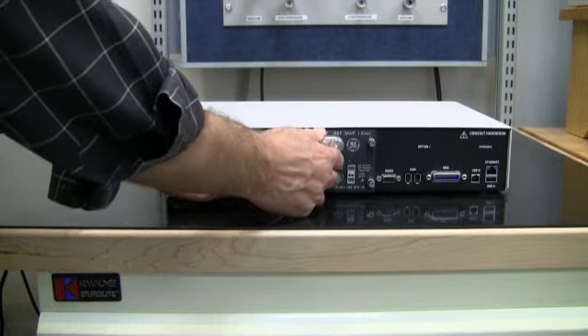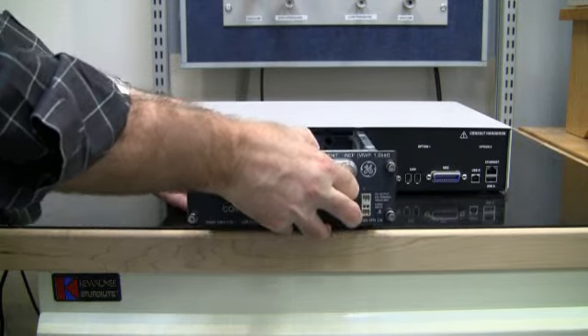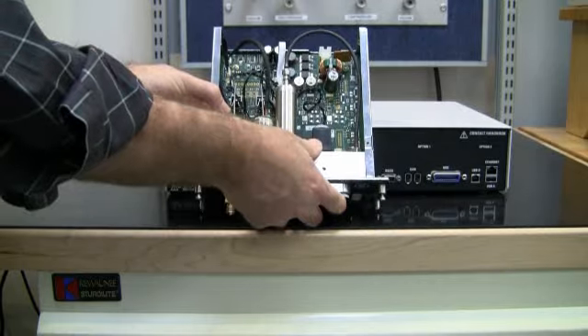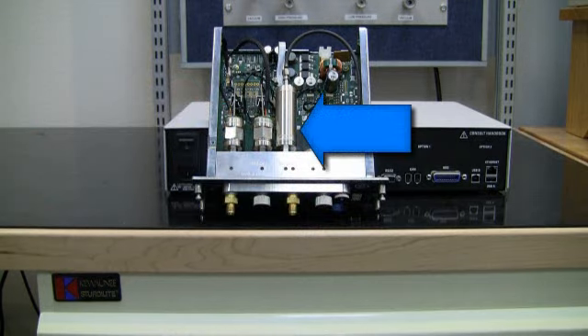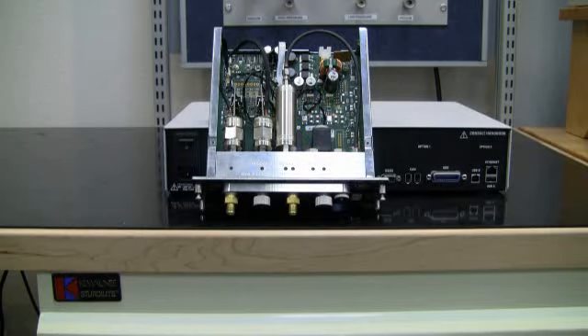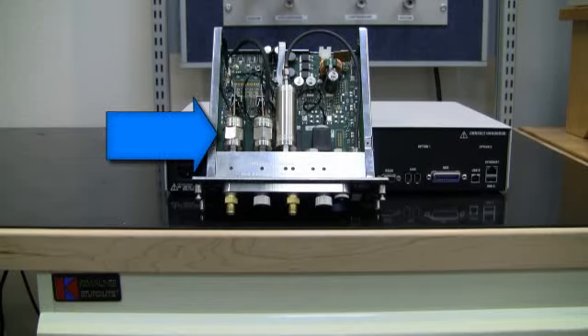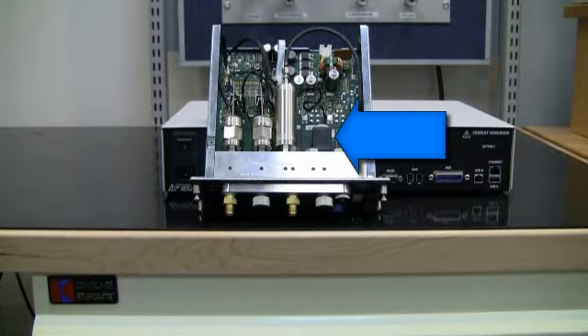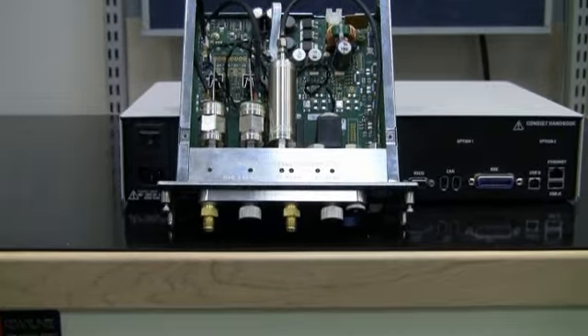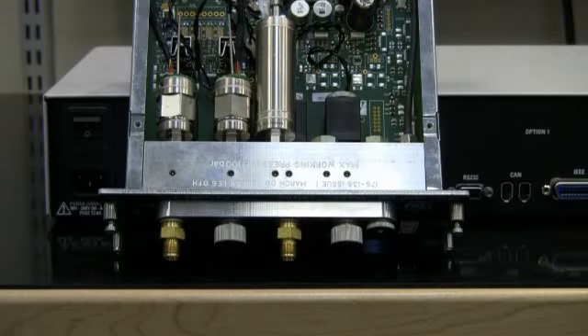For demonstration purposes, we have already removed the top cover of the control module. The control module includes the main pressure sensor, the optional barometric reference sensor which allows operation in absolute mode, the supply and vacuum pressure sensors, and the patented pulse width modulated control valves. Since all of the sensors that require recalibration are contained in the control module, there is no need to return the chassis when it is time for recalibration. A spare module on the shelf completely eliminates downtime.